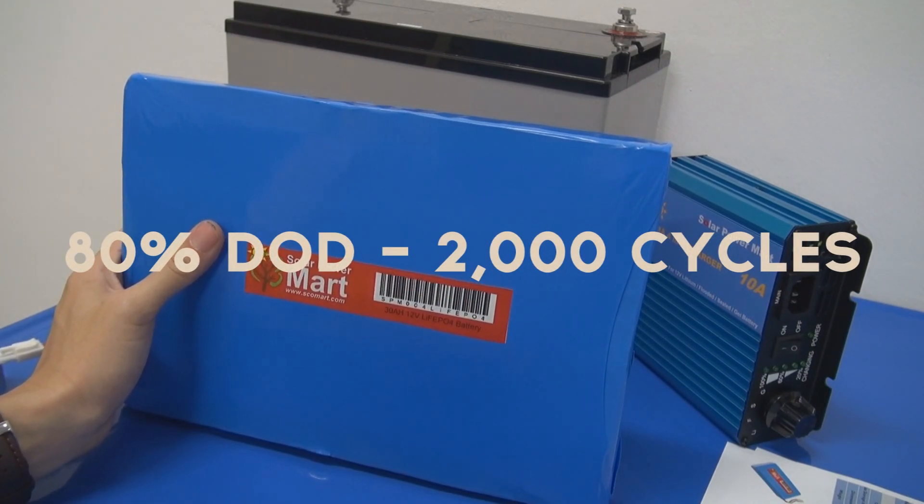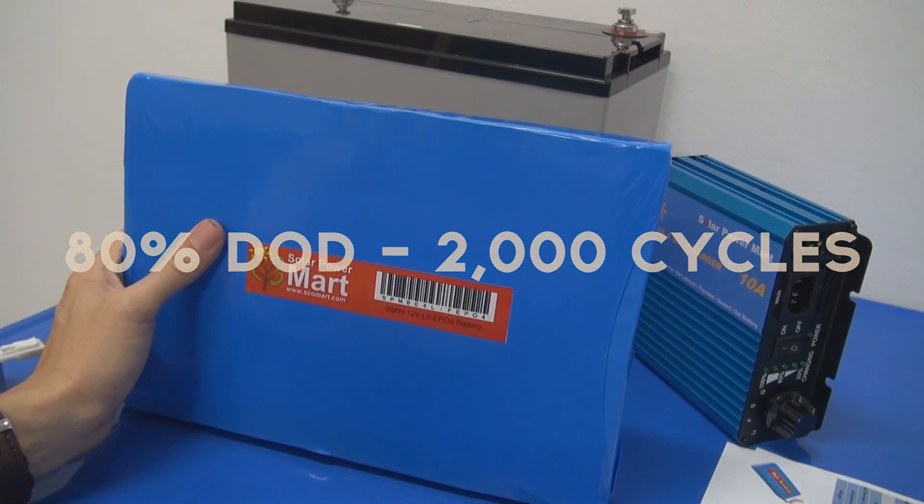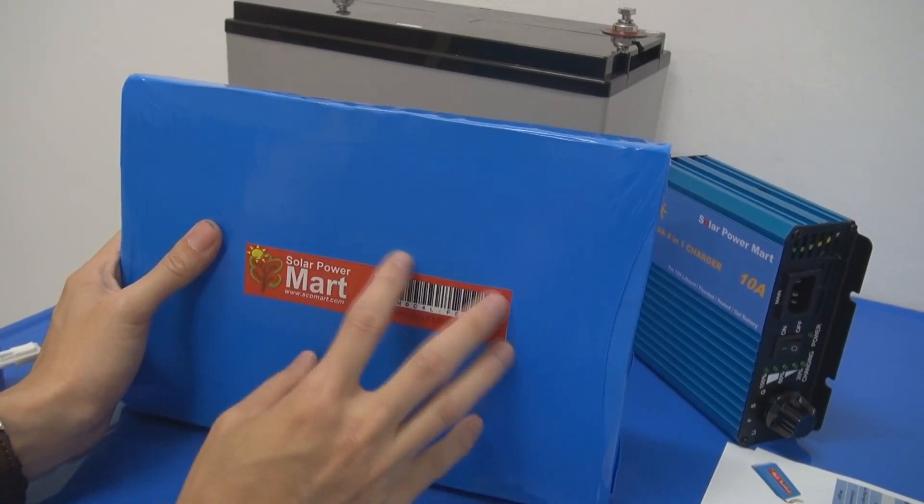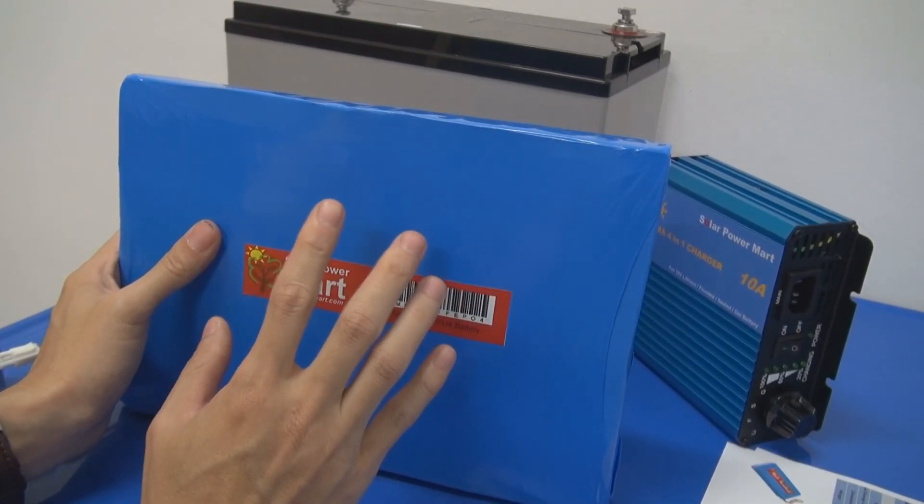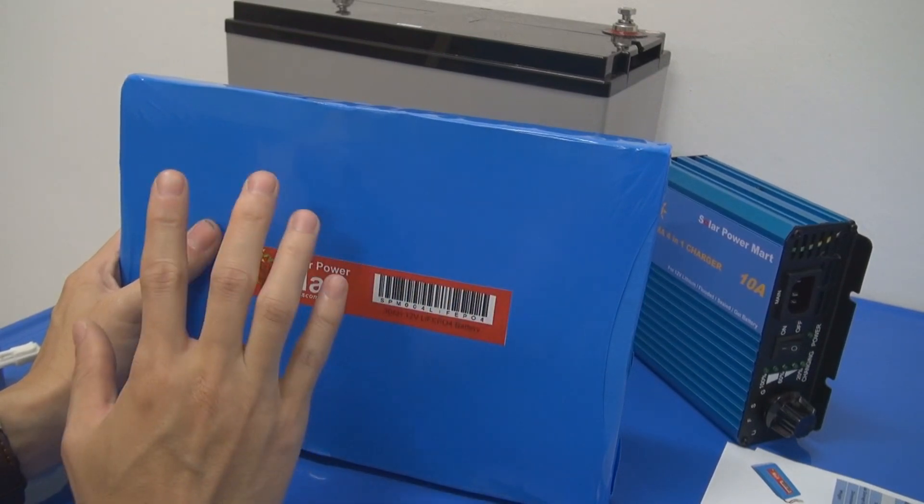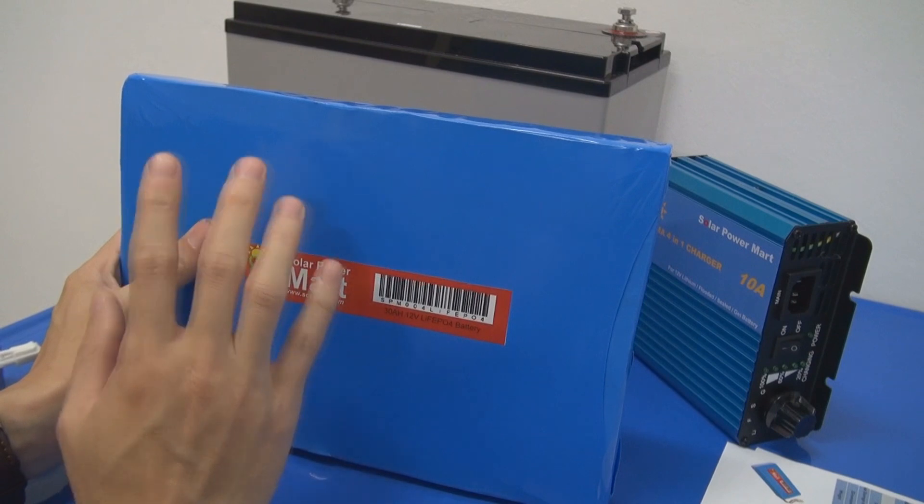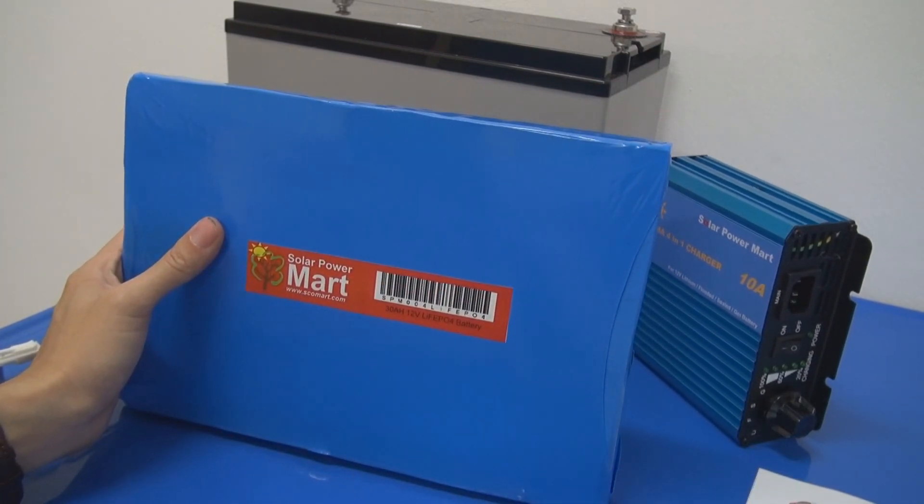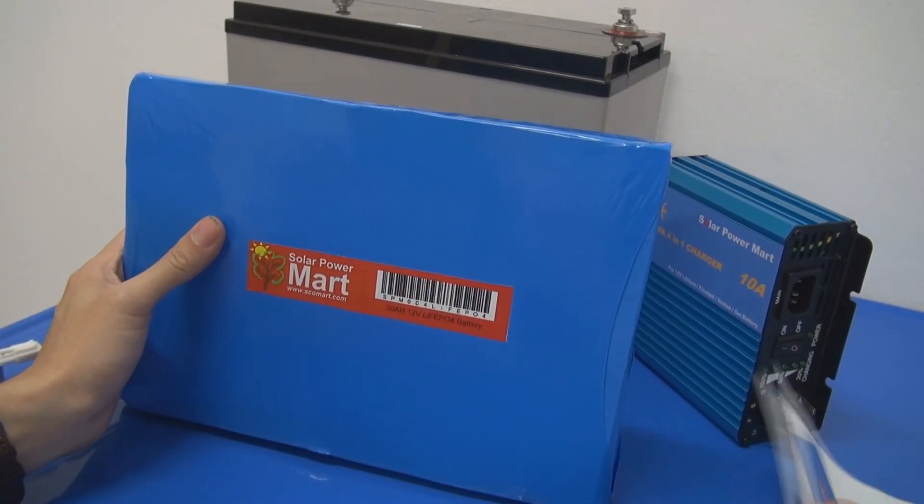But you do not need to do what we do in SLA or flood battery, whereby if the temperature is too high, 25C to 35C, you need to cut the cycle life in half. But for lithium battery, you don't need to do that. Why? Because lithium battery itself, especially LiFePO4—I'm talking about LiFePO4, not lithium ion or lithium polymer, those are different kinds of batteries.